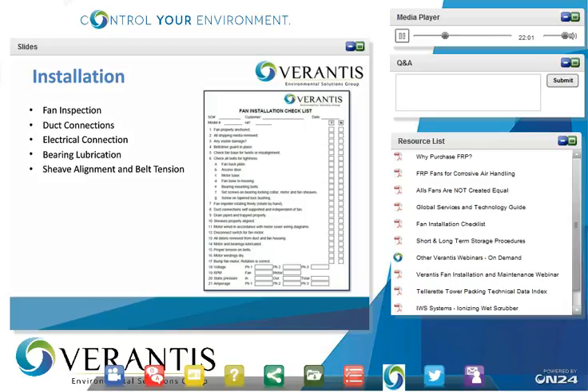In this section, we're going to cover fan inspection, duct connections, electrical connection, bearing lubrication, sheave alignment, and belt tension. On this page is also a fan installation checklist, and basically it wants to make sure the fan is properly anchored, all shipping media has been removed, and are there any visible damages to the fan.